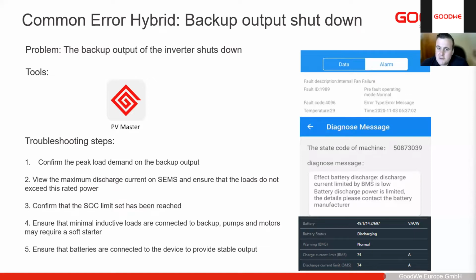Another example you'll see here in the alarms page, you've got internal fan failure. Please note this does not mean that there's a fail internal to the device that failed. This is actually backup overload. 4096 is the code for backup overload. Our devices don't have internal fans on most of our models, so we don't actually have a flag for that. It's an old historic name that they've used, which needs to be changed, but it's backup overload. That's what this error code means.